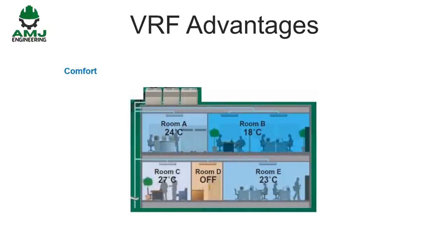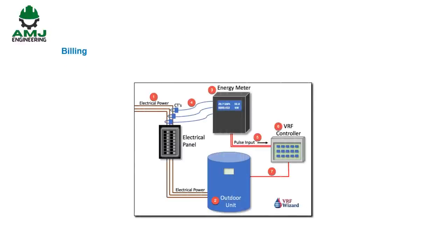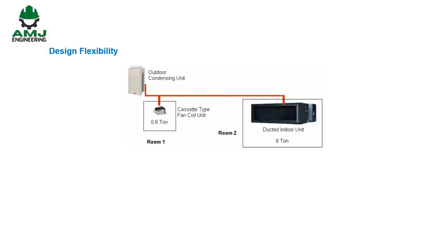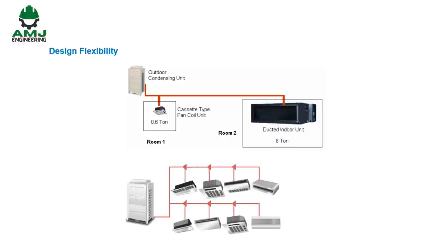Let us list some of the main VRF advantages. In terms of comfort, the main advantage of a variable refrigerant flow system is its ability to respond individually to fluctuations in space load conditions. The user can set the ambient temperature of each room as per his requirements, and the system will automatically adjust the refrigerant flow to suit the requirement. From a business point of view, VRF systems can generate separate billing that makes individualized billing easier. Design flexibility. A single condensing unit can be connected to a wide range of indoor units of varying capacity. Example: 0.5 to 8 tons, duct or ductless configurations such as ceiling recessed, wall-mounted, and floor console. Current products enable up to 48 indoor units to be supplied by a single condensing unit.